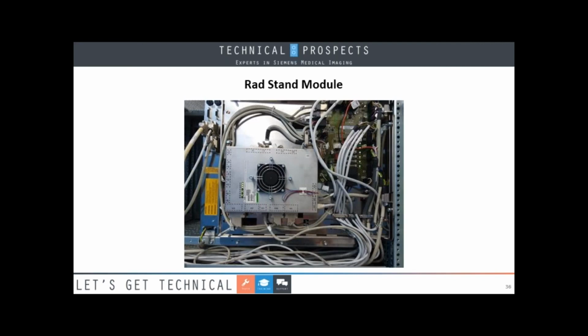When that generator or power cabinet is booting up, the table, overhead tube, and wall stand are given power. The rad stand module or CAN control board is looking for feedback from these components. So if all the potentiometers, encoders, motor controllers, and motors answer back properly, the CAN control is going to close and allow for movement.